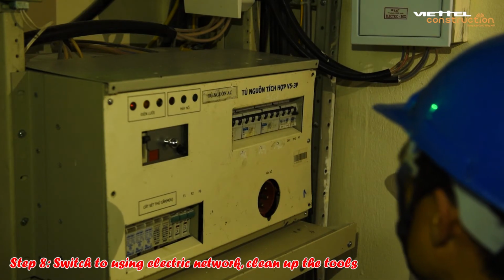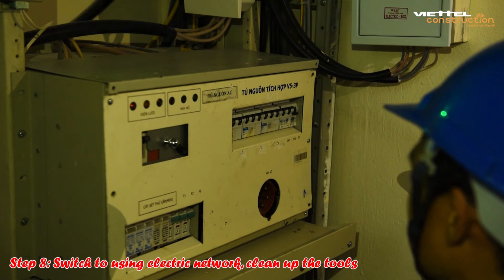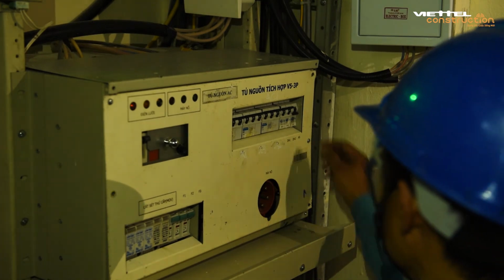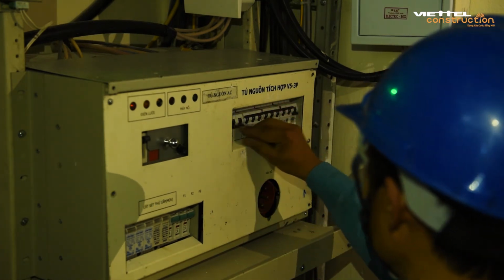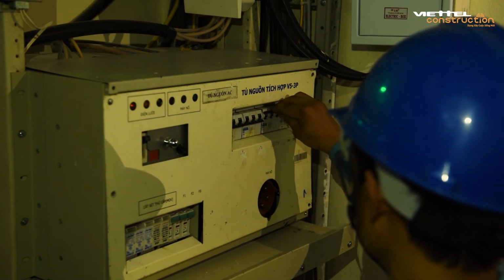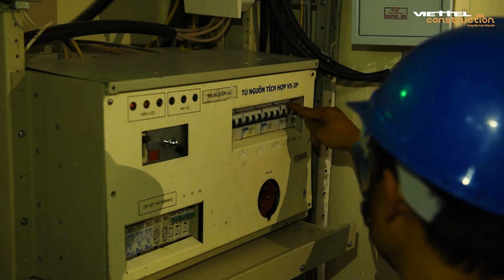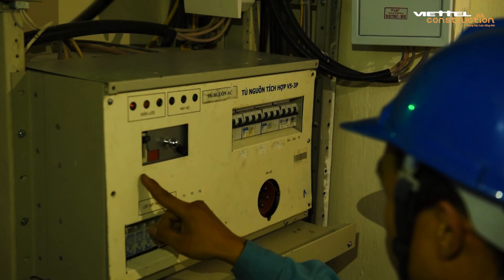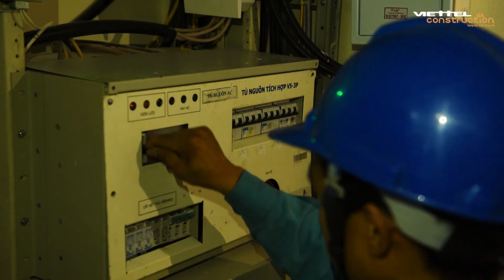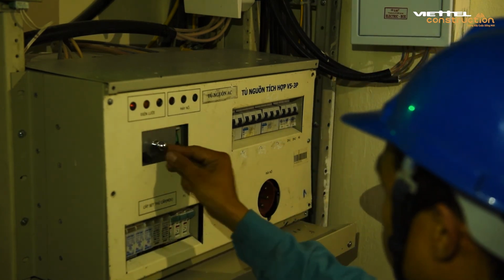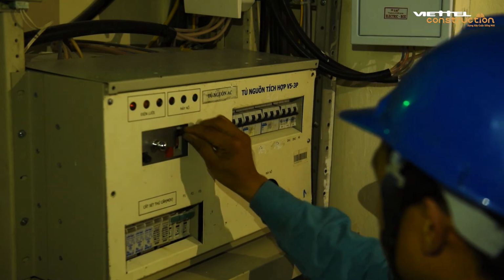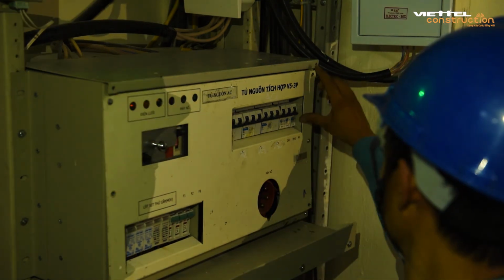Step 8. Switch to using the electric network. Clean up the tools. When the electric network is available and stable, reduce the load gradually for the machine and proceed to disconnect the load from the machine. The load should be reduced slowly from the largest to the smallest, then disconnect the generator from the load. Let the machine idle for 5 minutes to cool down, then turn it off properly.